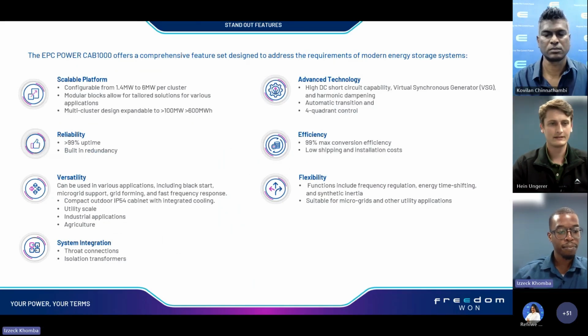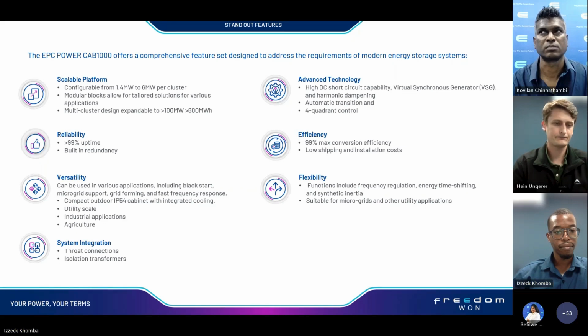Thanks for that, Isaac. Some of the unique selling points of this inverter: it's a very scalable platform, configurable from 1.4 to 5.6 megawatts on a single isolation transformer. You can use those modular clusters to build bigger capacity should you need to. The system is designed with redundancy in mind on its internal components, and it's designed for greater than 99% uptime.